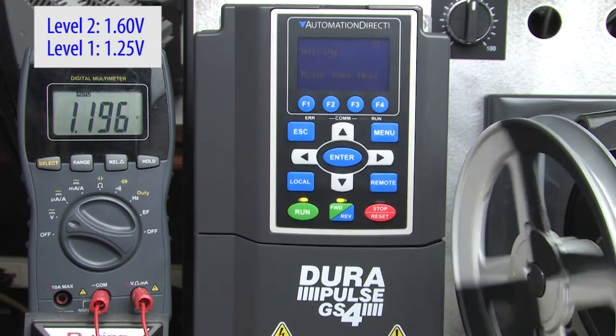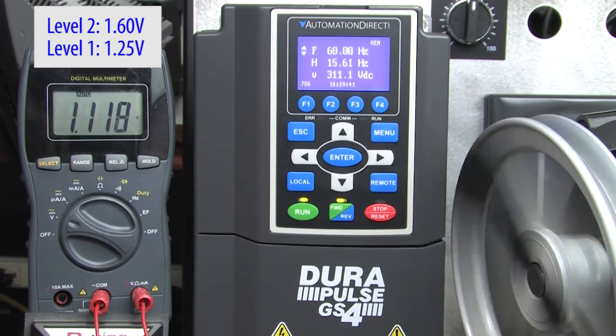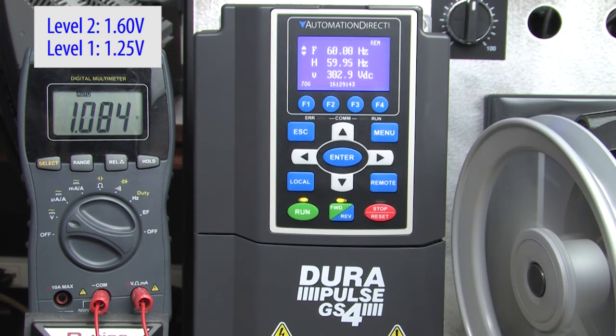If we cool the sensor off, the motor resumes speed and the fault goes away after the voltage has stayed below level 1 for that 5 second delay we set. That level 1 delay works on level 1's heating and cooling transitions. If we heat it up again, it passes level 1, drops a frequency and generates a fault just like before.